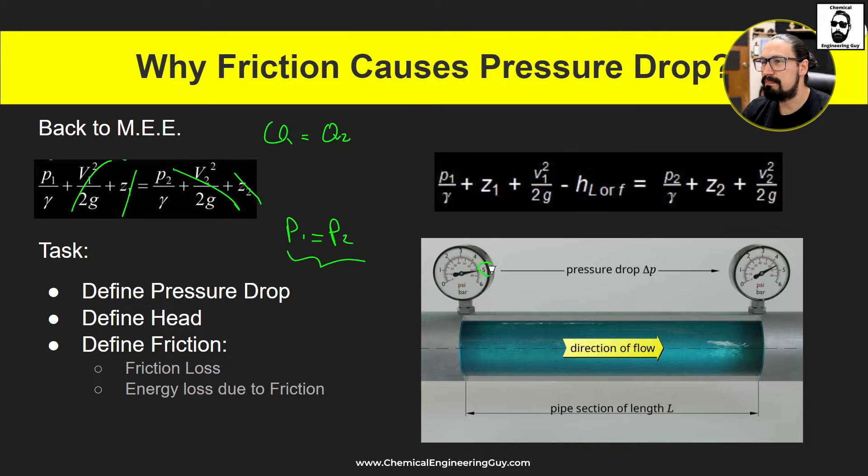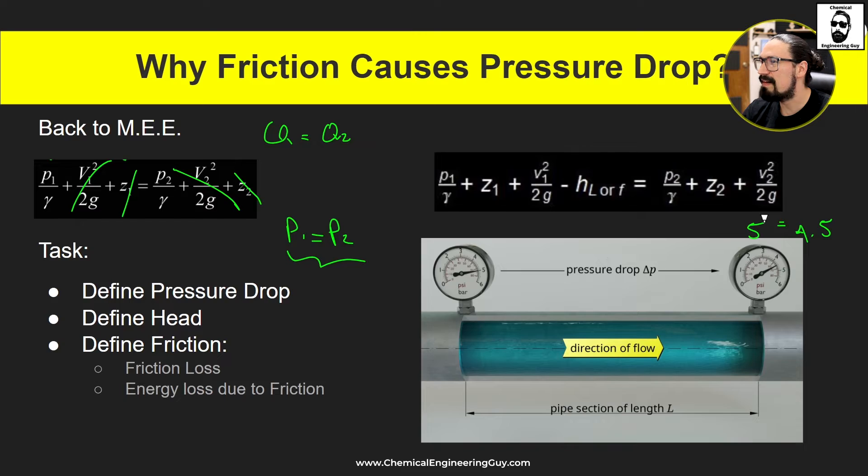If we add a manometer at the inlet and another at the outlet, we encounter an actual pressure drop: five bar here and 4.5 bar there. You might say it's measurement error, but in reality it is an actual pressure drop. The answer to why we have a pressure drop when there's nothing in between is that there is something — it's a trajectory-dependent variable, and we're talking about friction loss.